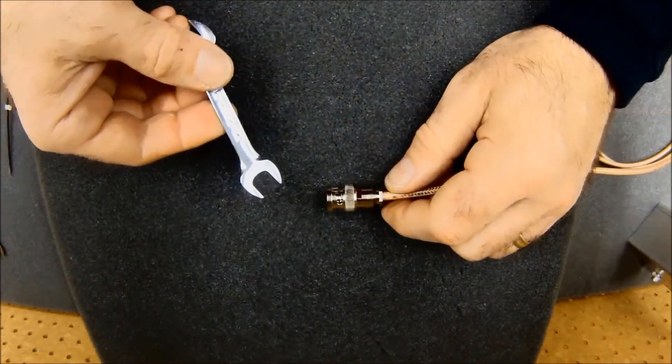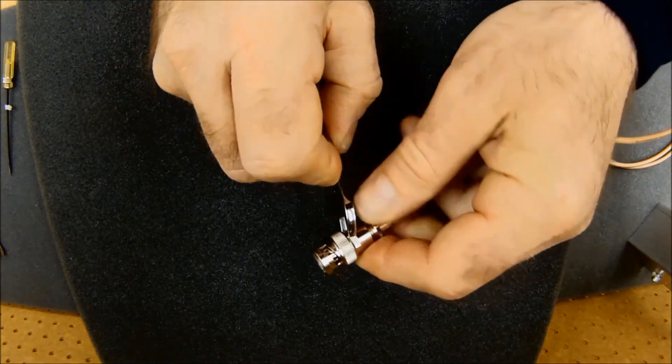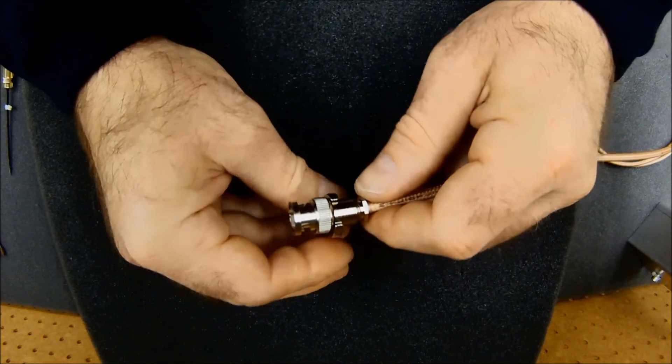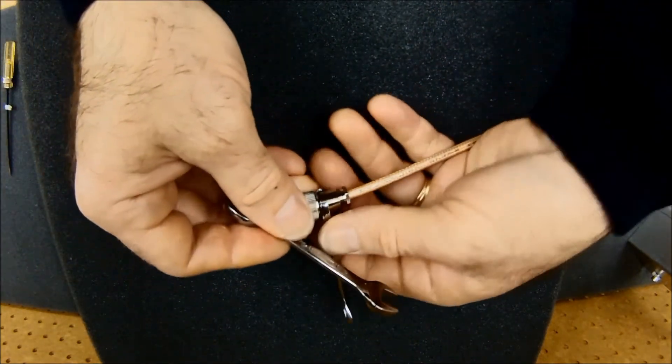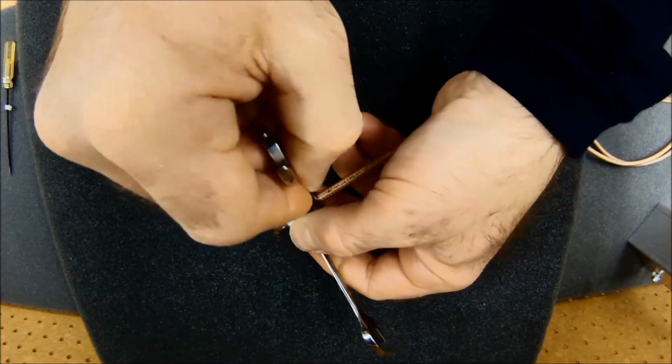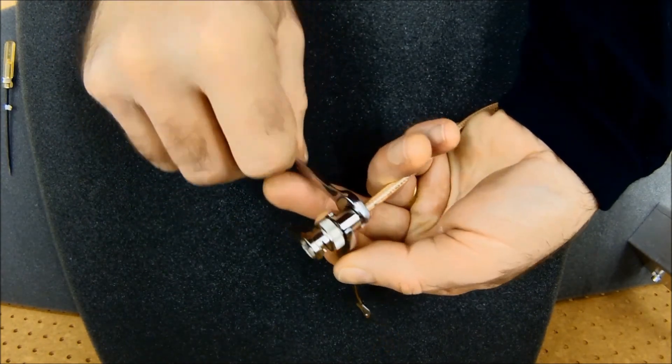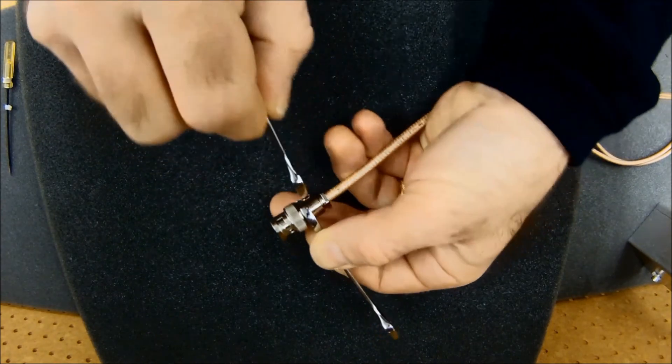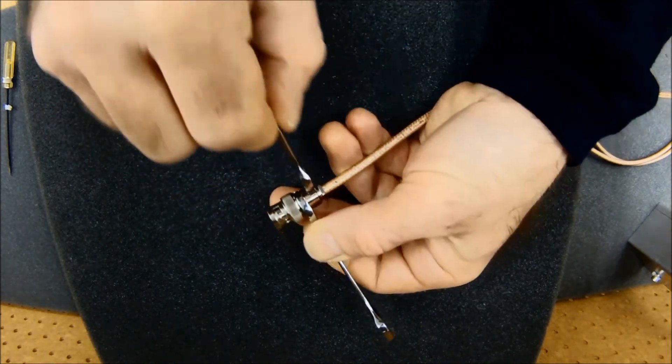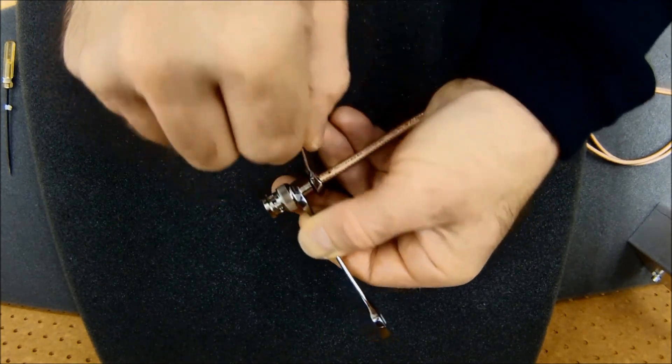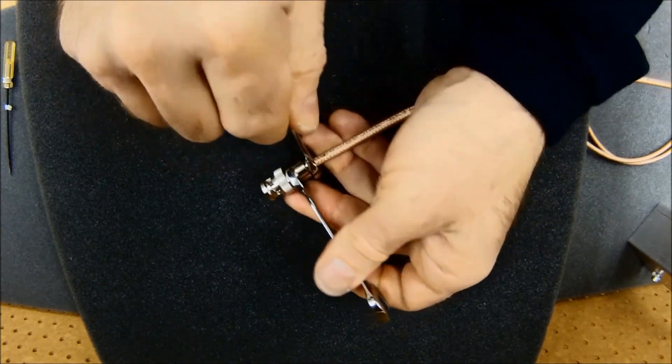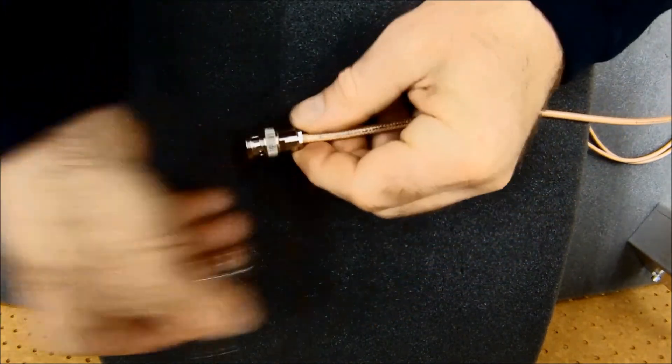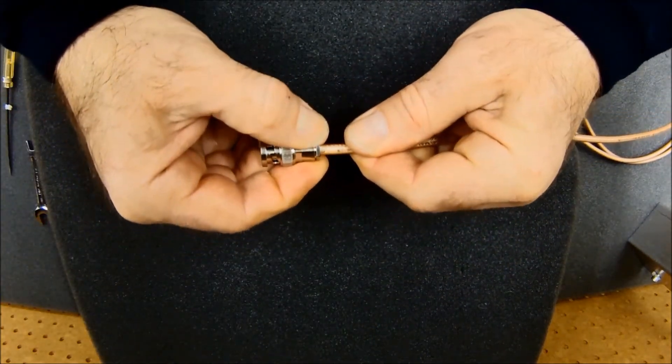Now at this point what I'm going to do is I'm just going to take a pair of 3 eighths inch wrenches. Slip one onto the body of the connector and use the other to tighten up the back nut. It's important not to over tighten this back nut or it ends up cutting off strands of that braid. So just bring it down until it's good and snug. It's got a little bit of pressure on the gasket. And this is rock solid. It won't pull off.